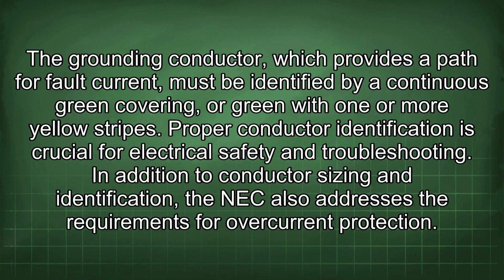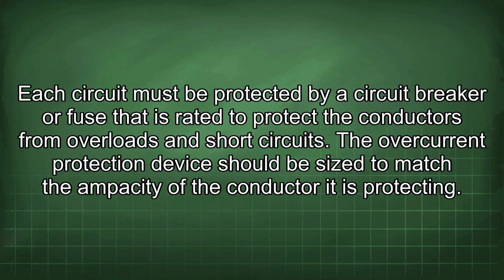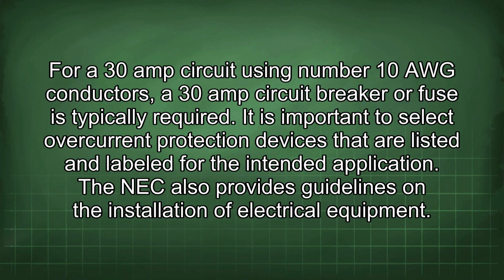In addition to conductor sizing and identification, the NEC also addresses the requirements for overcurrent protection. Each circuit must be protected by a circuit breaker or fuse that is rated to protect the conductors from overloads and short circuits. The overcurrent protection device should be sized to match the ampacity of the conductor it is protecting. For a 30 amp circuit using number 10 AWG conductors, a 30 amp circuit breaker or fuse is typically required. It is important to select overcurrent protection devices that are listed and labeled for the intended application.